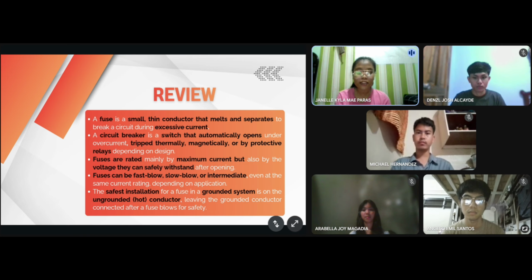The safest installation for a fuse in a grounded system is on the ungrounded or hot conductor, leaving the grounded conductor connected after the fuse blows for safety. Next slide.